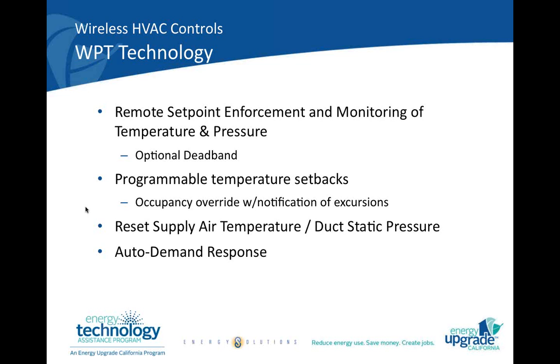If a central energy management system or building management system is being used to control the central equipment in the building, then WPTs can integrate with that system and can do strategies like resetting the supply air temperature or resetting the duct static pressure to allow additional energy savings in times of low or high load. Finally, if you're enrolled in a demand response program, WPTs can be used to automatically respond to demand response events and bring down your peak load during those times.